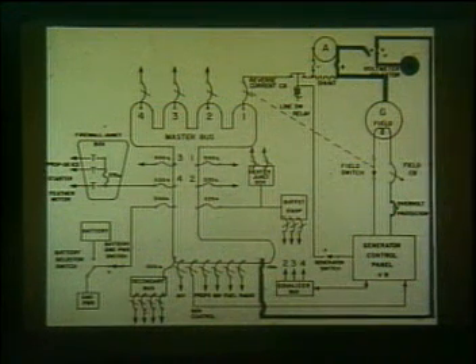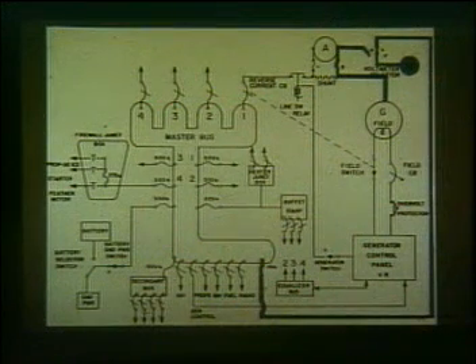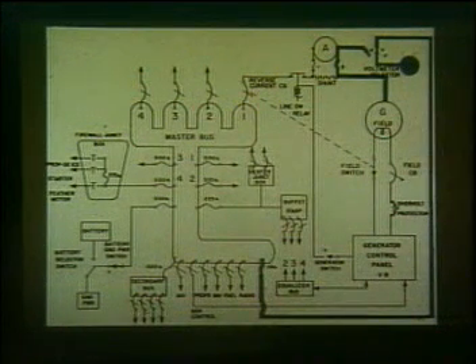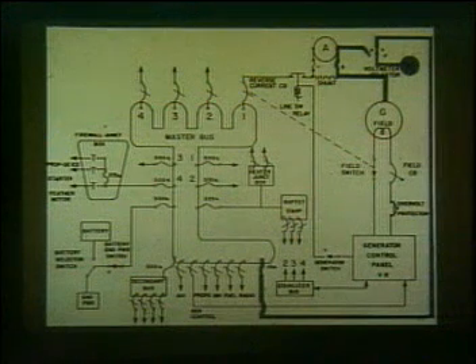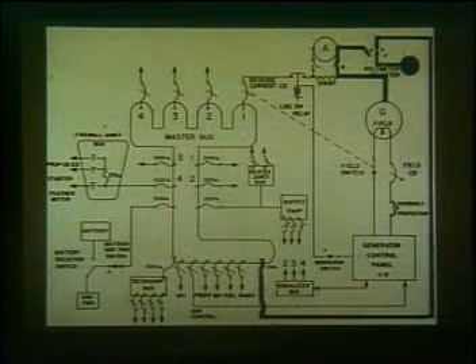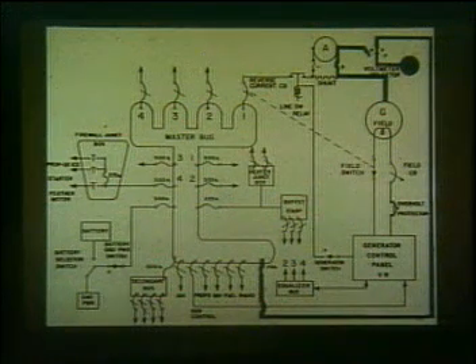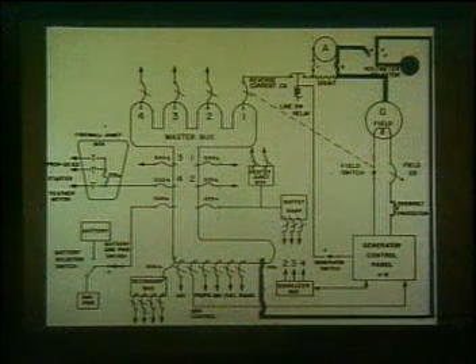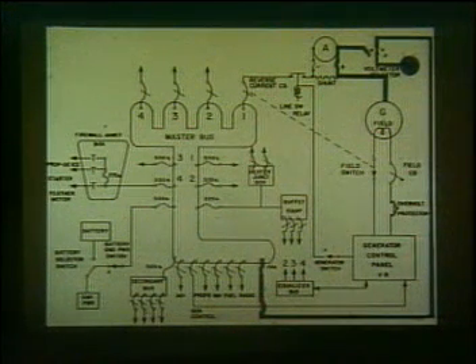When the voltmeter selector switch is in the bus position, power is provided through a 10 amp fuse through a selector switch to the voltmeter. This fuse only protects the voltmeter in the bus position. When an individual generator is selected, voltage for that generator travels through the ammeter positive fuse to the voltmeter. This fuse will protect the voltmeter when in a selected generator position.